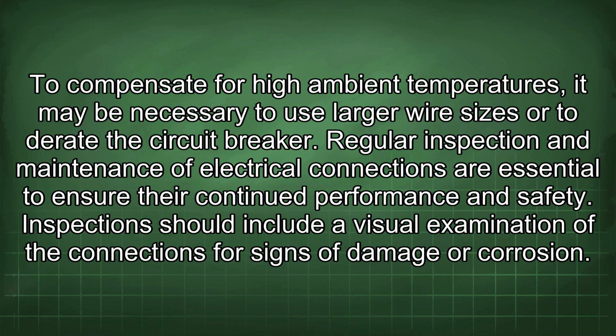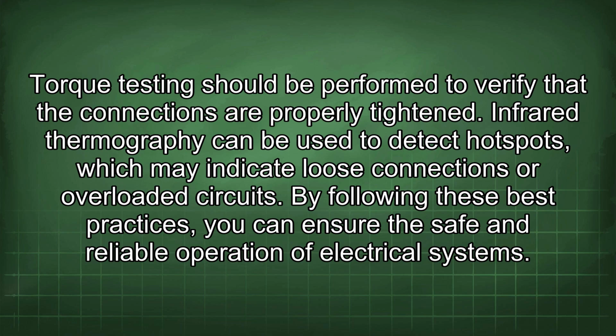Inspection should include a visual examination of the connections for signs of damage or corrosion. Torque testing should be performed to verify that the connections are properly tightened. Infrared thermography can be used to detect hotspots, which may indicate loose connections or overloaded circuits. By following these best practices, you can ensure the safe and reliable operation of electrical systems.